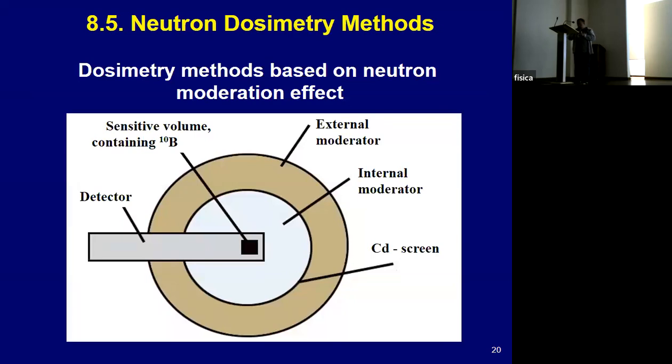And one more mode that we need is to measure dosimetry from neutrons. All currently used neutron dosimeters and radiometers for operational measurements are based on the same physical principle: the registration of the thermal neutron flux density in the central part of the detector. Usually, this part is enriched in boron-10, which has a big cross section for the interaction with neutrons, especially thermal neutrons.